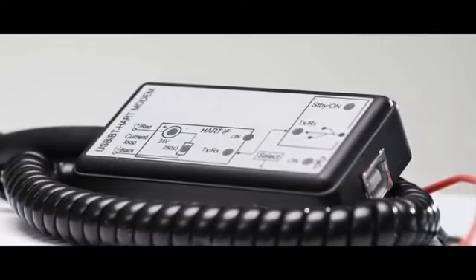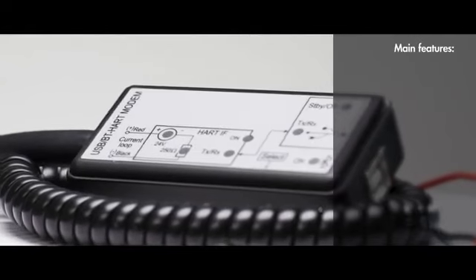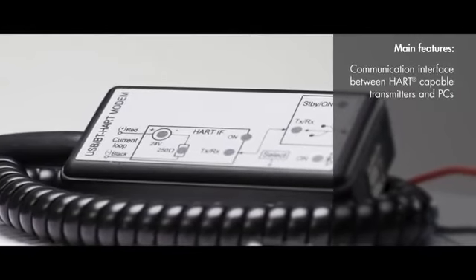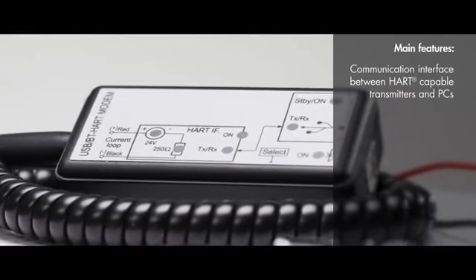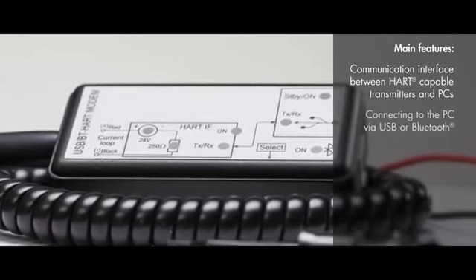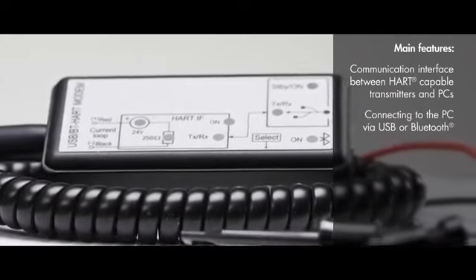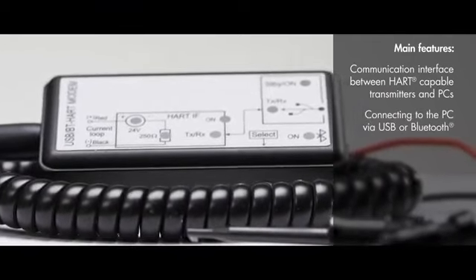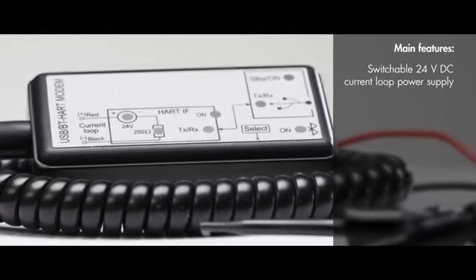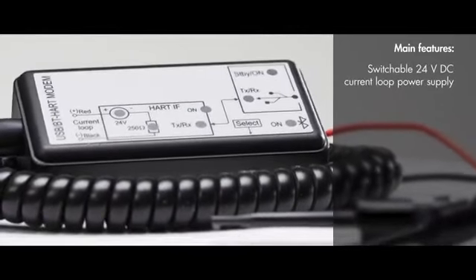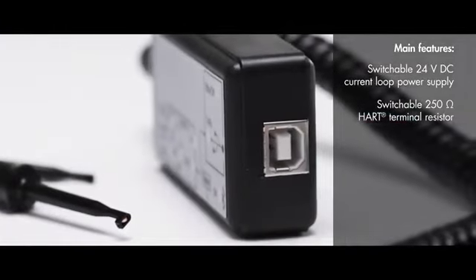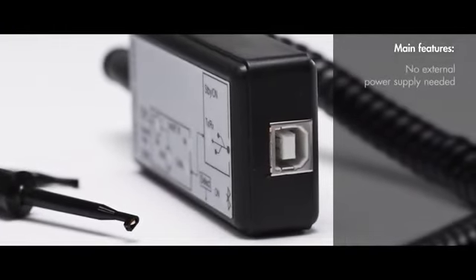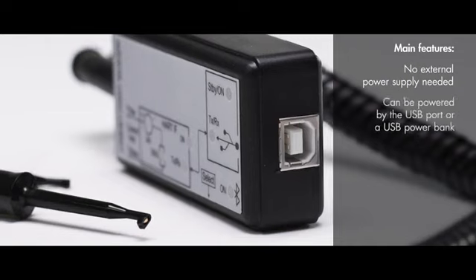Main features of Nivelco's Unicom SAT-504 are the following. Communication interface between HART-capable transmitters and PCs. Connecting to the PC via USB or Bluetooth. Switchable 24-volt DC current loop power supply. Switchable 250-ohm HART terminal resistor. No external power supply needed.